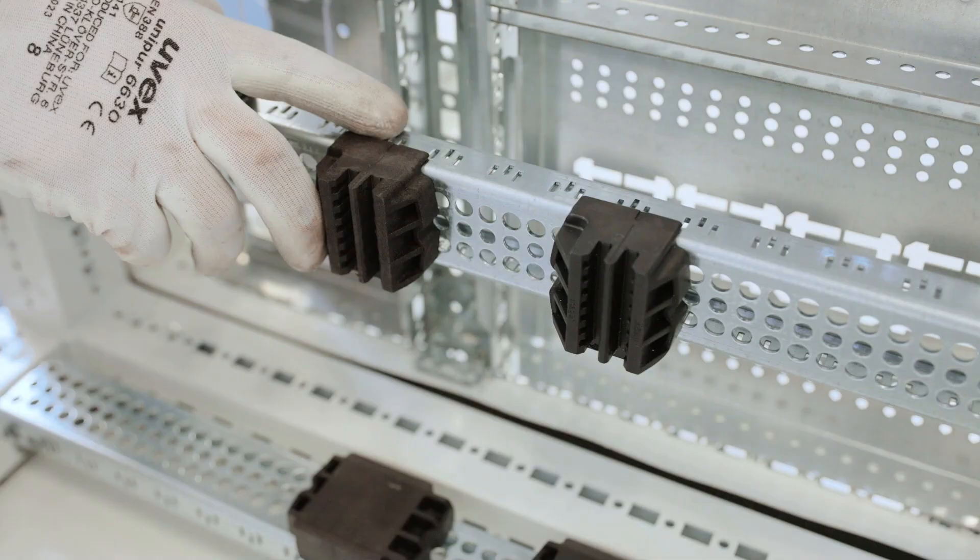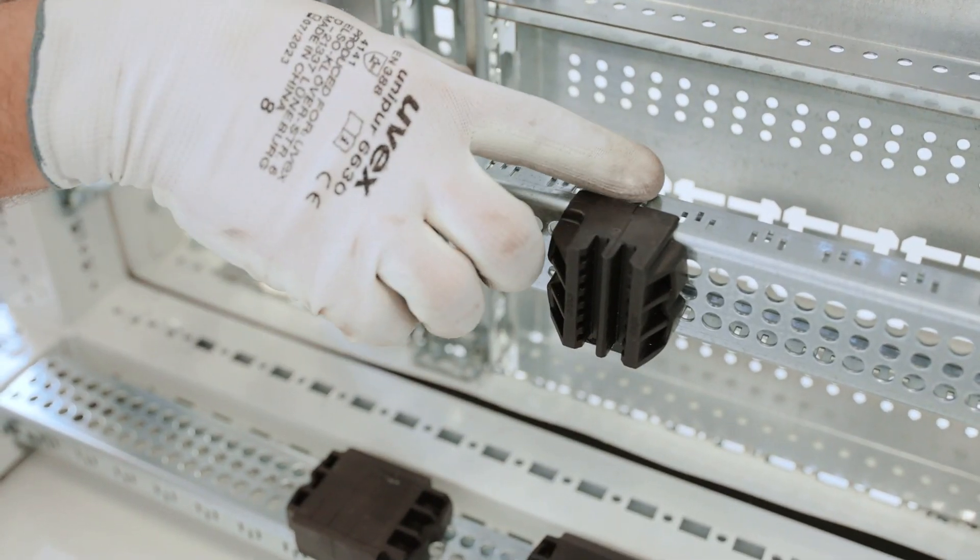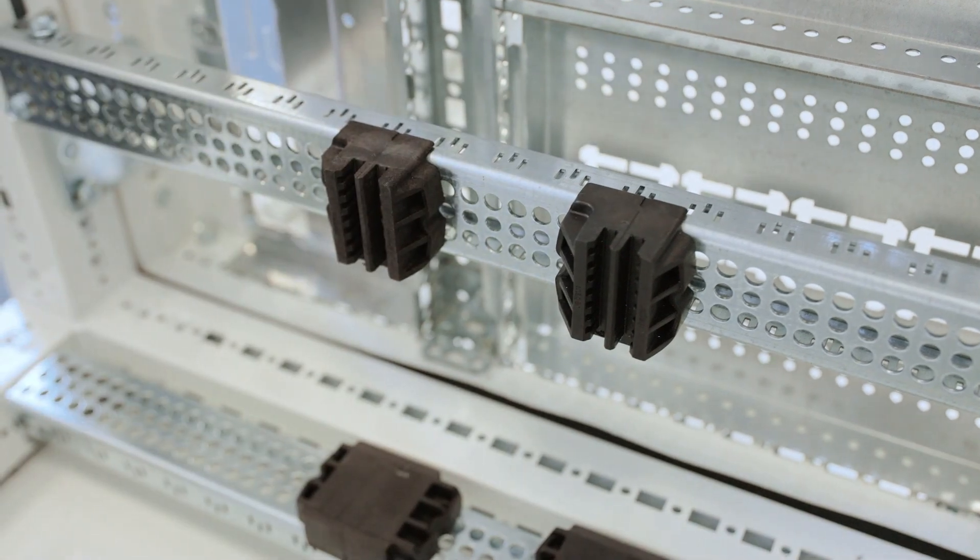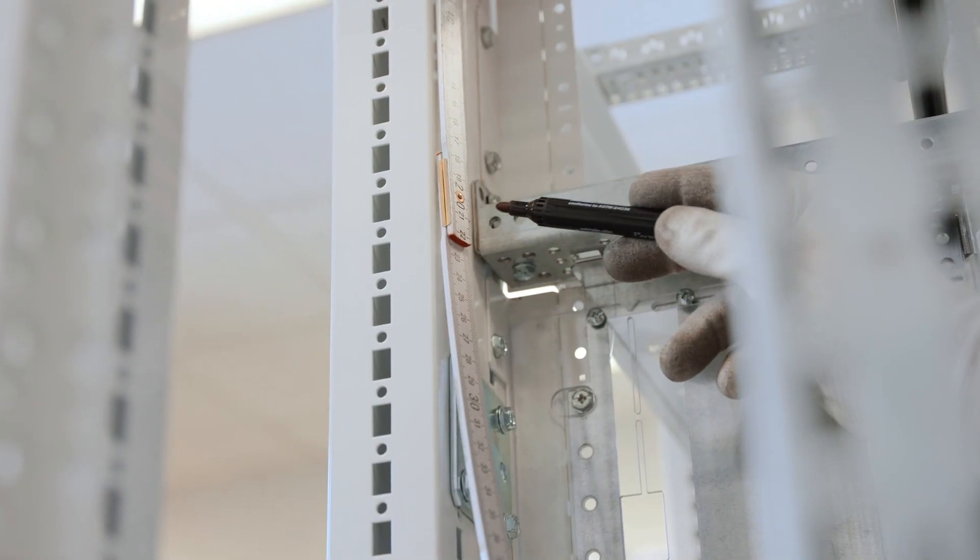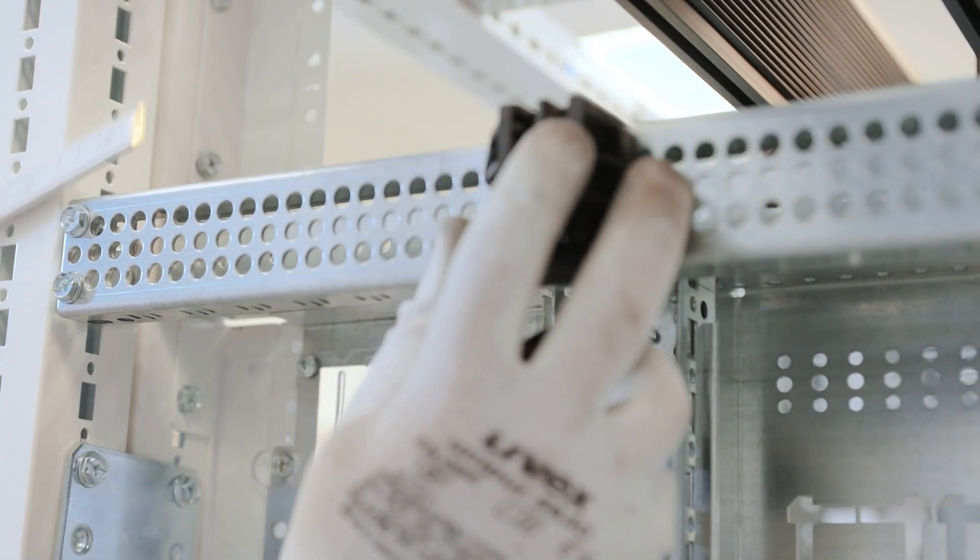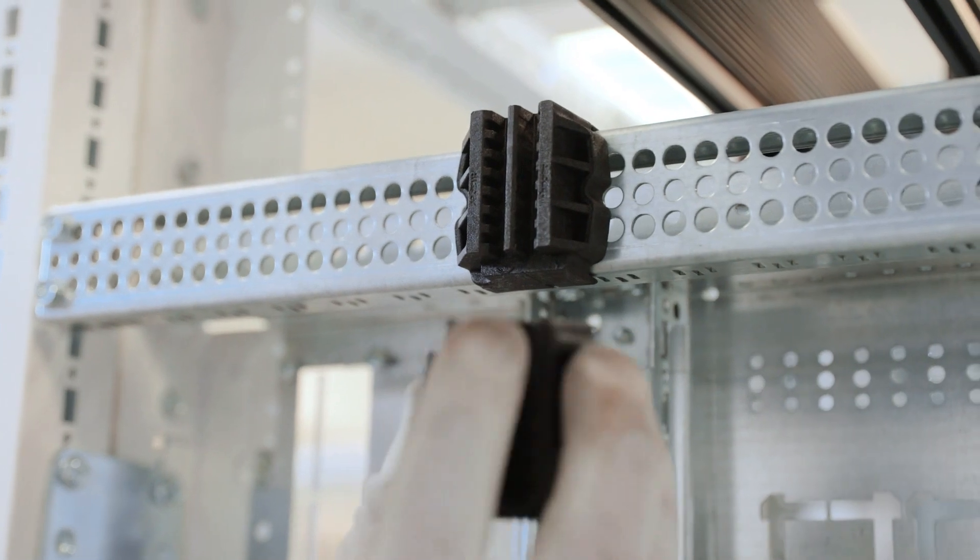Put in the bar and tighten the screws. Put the supports in at the same distance as the others. For the upper rail, the distance is 20 centimeters. Always put in the supports at the correct phase distance.